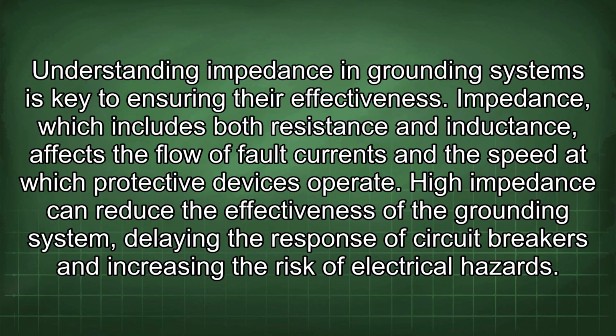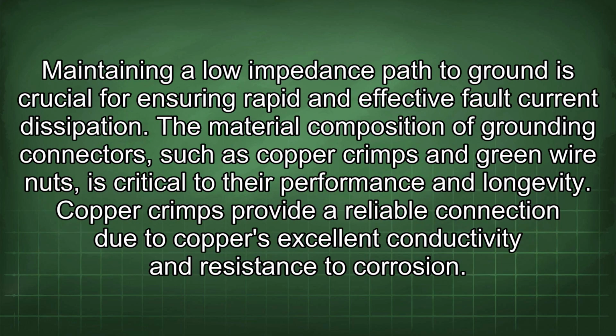Understanding impedance in grounding systems is key to ensuring their effectiveness. Impedance, which includes both resistance and inductance, affects the flow of fault currents and the speed at which protective devices operate. High impedance can reduce the effectiveness of the grounding system, delaying the response of circuit breakers and increasing the risk of electrical hazards. Maintaining a low impedance path to ground is crucial for ensuring rapid and effective fault current dissipation. The material composition of grounding connectors, such as copper crimps and green wire nuts, is critical to their performance and longevity.